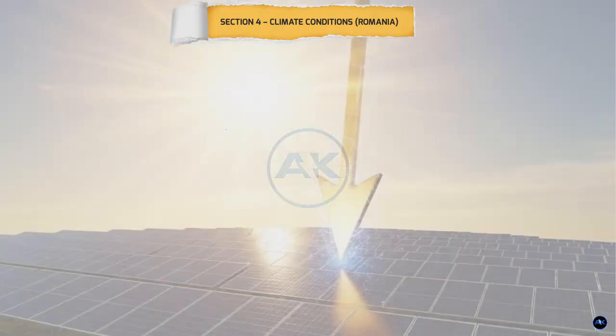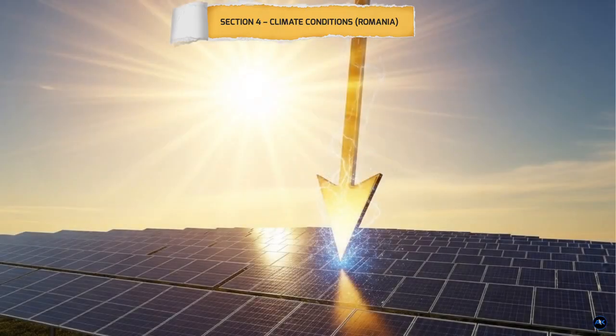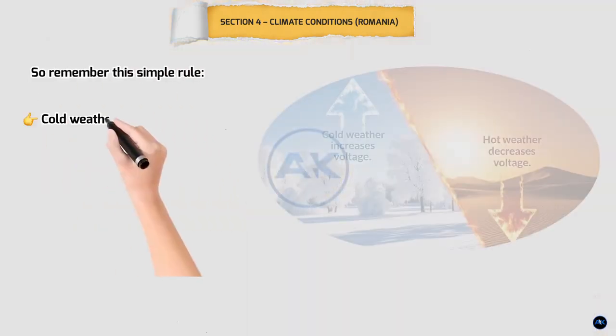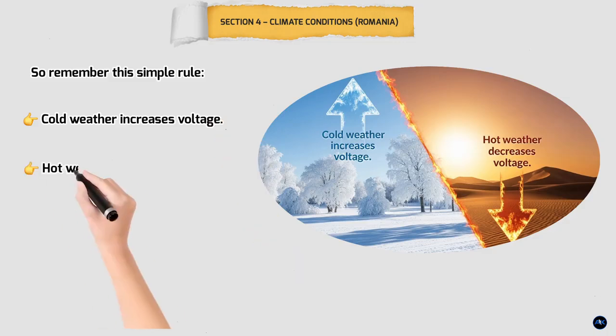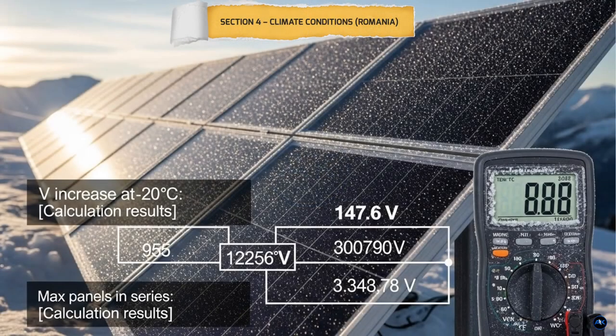When it's hot, solar panel voltage drops, even though the panels may still produce high power. So remember this simple rule. Cold weather increases voltage, hot weather decreases voltage. That's why all solar string calculations must be based on the coldest expected temperature, not summer conditions. In the next section, we'll calculate exactly how much the voltage increases at -20 degrees and how many panels we can safely connect in series.